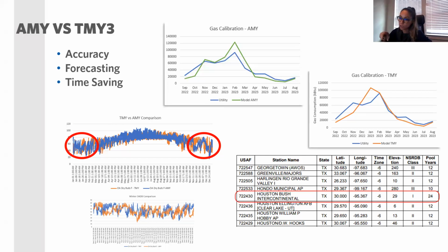And then when we actually compare the outside dry-bulb temperature, because the system was running off of the outside air control, the boilers were locking out based on outside temperature. So we can see that clearly when we look at this, that's winter months, the temperature is very different between these two data sets. So it helps with the accuracy, it helps with time saving, so you don't have to play with different parameters for the calibration, and it also helps with the forecasting.